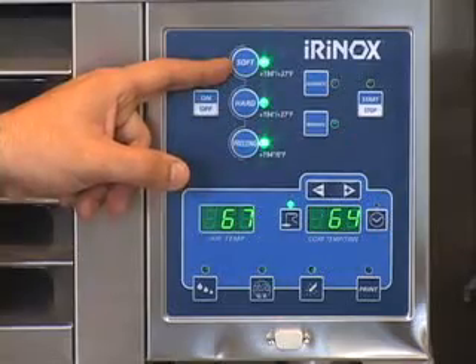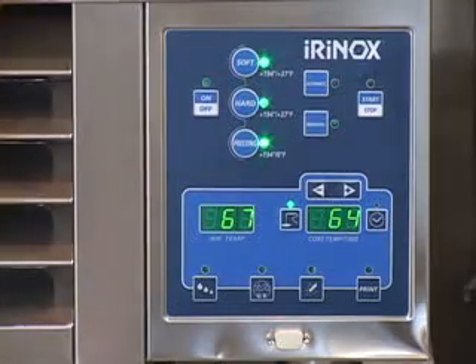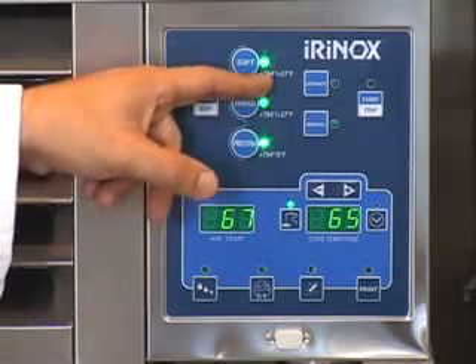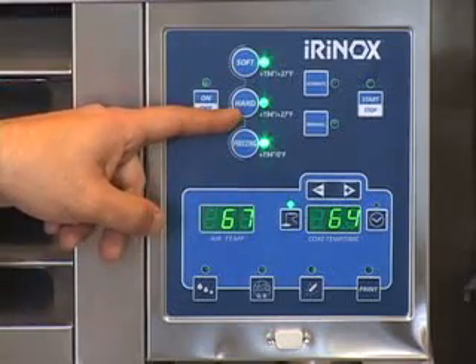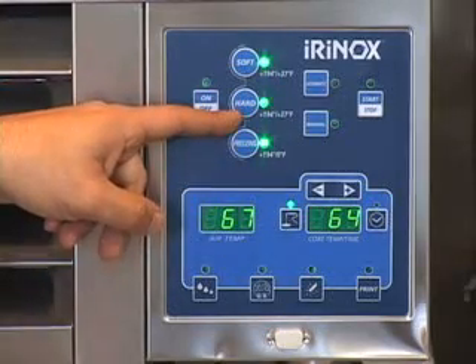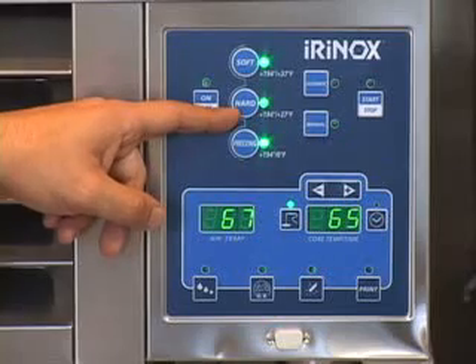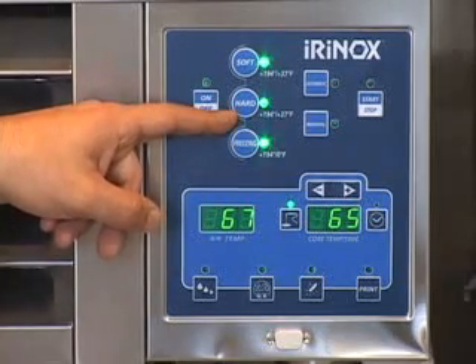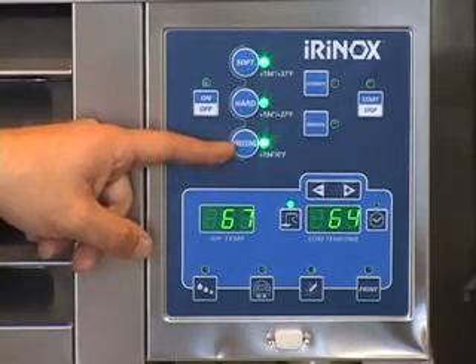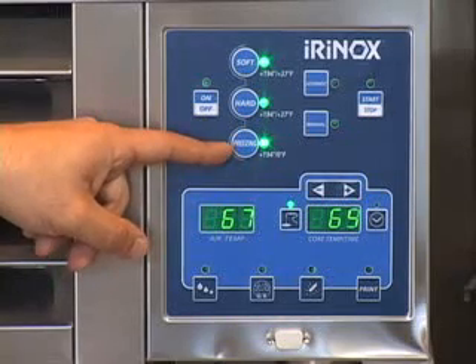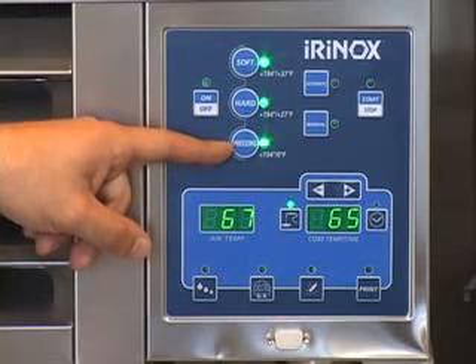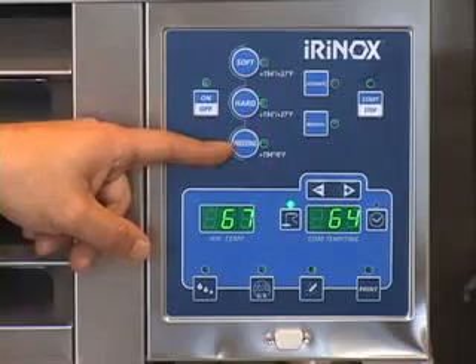Soft is a chilling cycle which will take product from 200 degrees or above at the core to 37 degrees in less than 90 minutes. Hard is also a chilling cycle which will, again, take product from 200 degrees at the core to below 37 degrees in 90 minutes. Shock freezing is a freeze cycle which will take product from above 200 degrees at the core to 0 degrees in 4 hours or less.